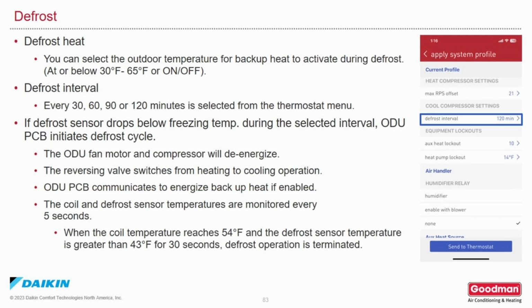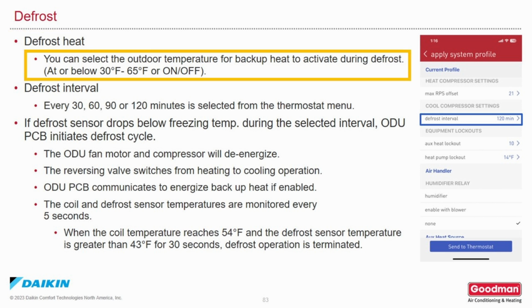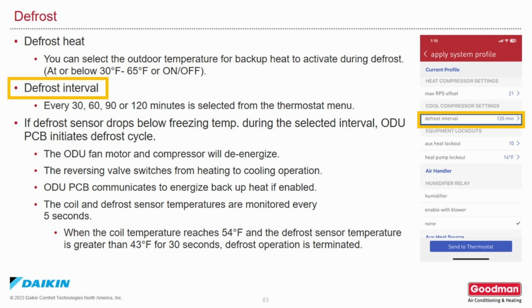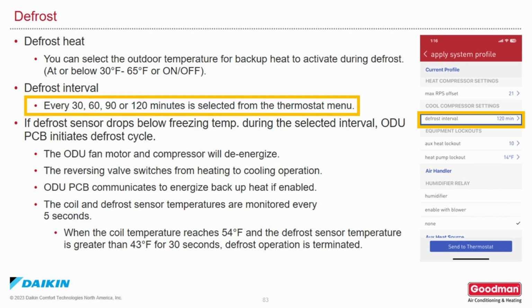So let's talk about defrost. Defrost heat. You can select the outdoor temperature for backup heat to activate during defrost, at or below 30 degrees Fahrenheit to 65 degrees Fahrenheit, or you can turn it on or off. So you can opt to use backup heat during defrost or not use backup heat during defrost. Defrost intervals are adjustable, 30, 60, 90, or 120 minutes between defrost cycles, selected from the thermostat menu.